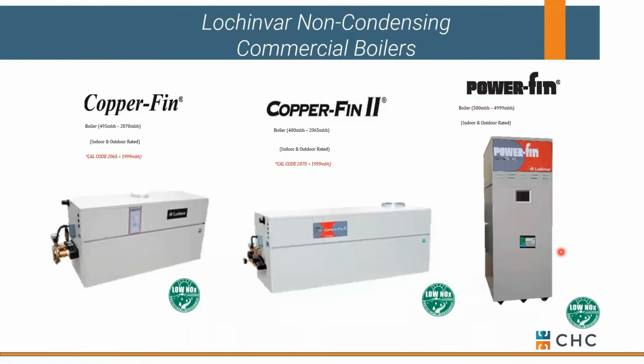Most boiler manufacturers are going to have two options for you. They're going to have their line separated between non-condensing boilers and condensing boilers. So non-condensing means there's going to be a minimum return temperature that you have to keep these at, okay? And in this case, these are all copper boilers. So I'm going to tell you minimum return right off the bat needs to be 130 degrees. And we'll talk about how you might protect these if your temperatures are lower than that. But you have options to go horizontal or vertical as it relates to your floor space.